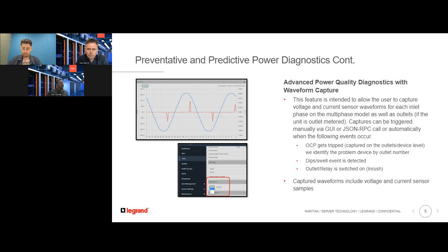So it's real-time data. The images are stored within the PDU. It's FIFO, kind of first in, first out. But this is key information in understanding I had a problem. What was the problem? And understanding it, because the harmonics are an issue with today's switch mode power supplies, but ultimately dips and swells are also a huge issue, and dips are one of the more common problems for data center power outages today, actually. So this is a great indicator of understanding what happened at a certain event, and being able to go back and look at the data as it happened in real time.